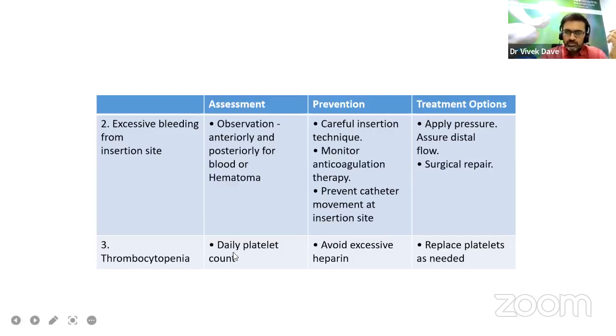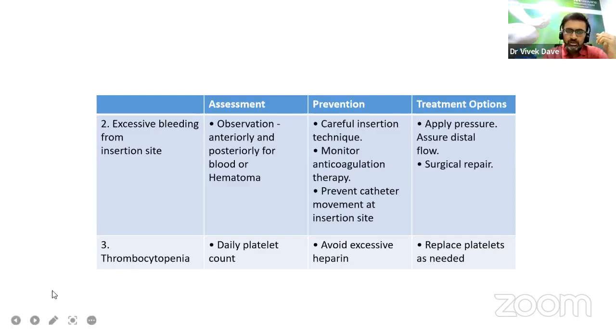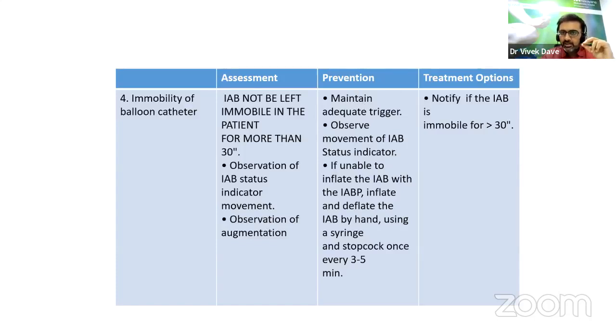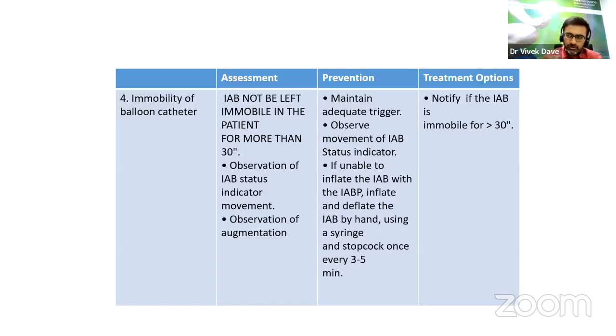Immobility of the balloon catheter: IABP should not be left immobile. Observe IABP status indicator movement and augmentation; maintain adequate trigger. If unable to inflate, inflate and deflate the IAB by hand using a syringe and stop-cock once every three to five minutes to prevent complications from immobility of the balloon catheter.